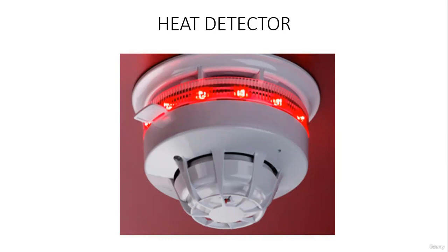So if you use a heat detector in a kitchen, or sometimes a smoke detector in a kitchen, usually in a kitchen there is smoke, there is heat, right? So that's a usual thing. So if we use a heat or smoke detector in a kitchen, that's not useful, right? It detects continuously, so that's a huge problem. So heat detectors and smoke detectors are used in rooms and halls and also in duct systems like that, right?